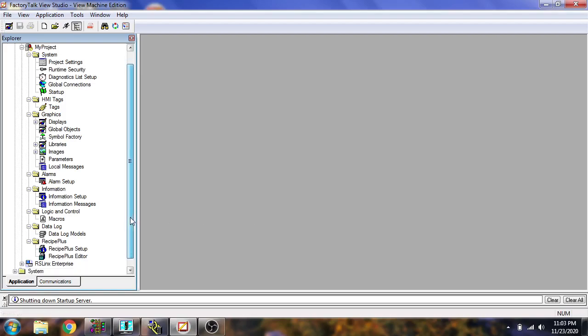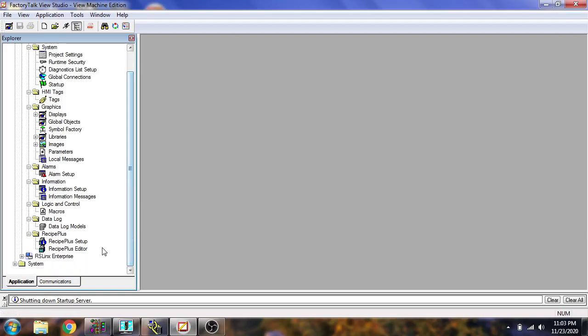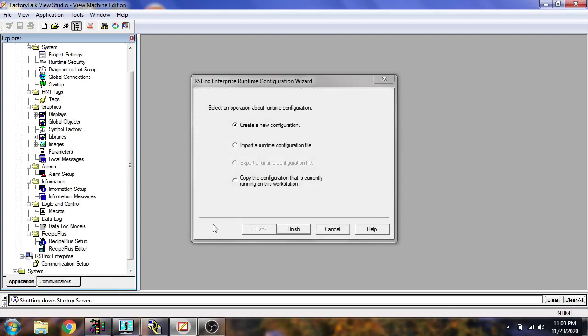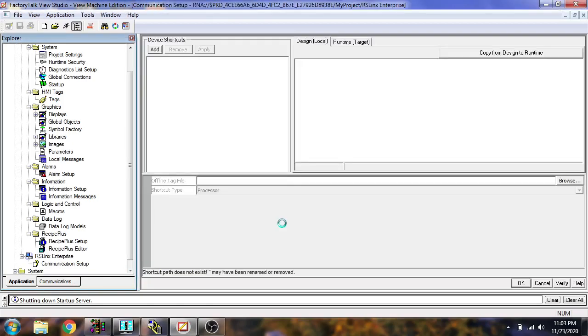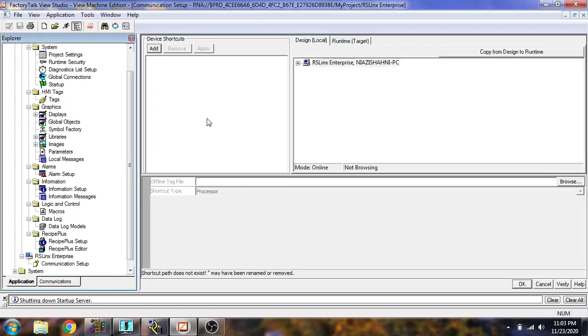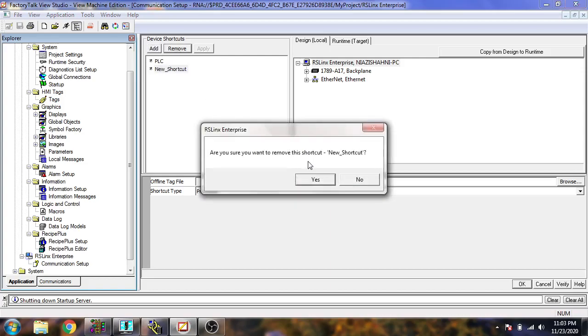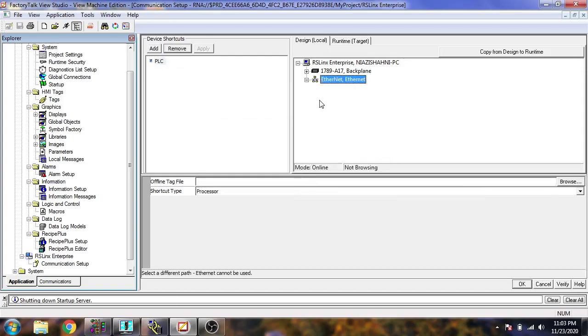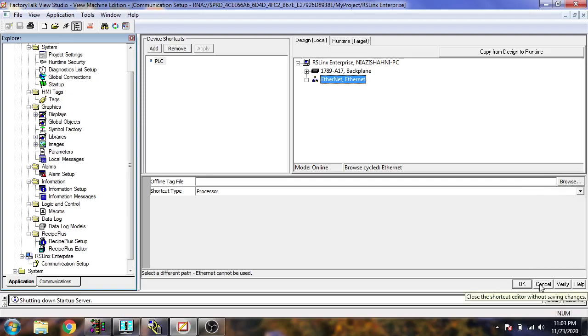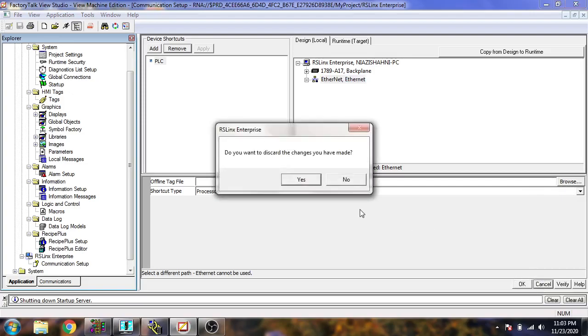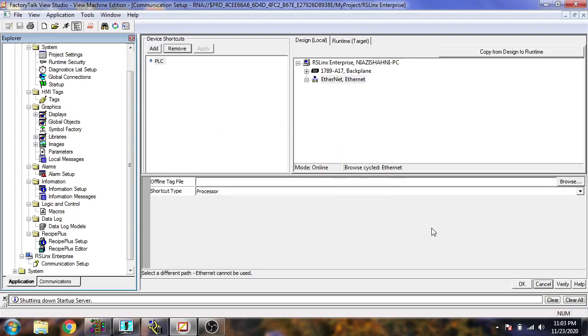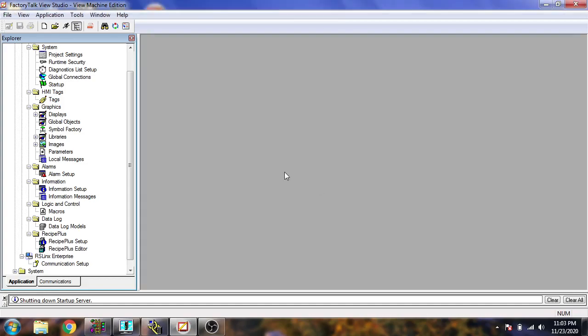I'm just showing you how you communicate to your RSLinx to your PLC. You will use RSLinx Enterprise and setup Communication Setup and create a new configuration. You will add a device which we will name my PLC, and you add then you just select your PLC there and you will connect that. Browse for tags - I have a browse offline tag available so you will check it from this. I'm going to cancel it, I just don't need to, yes I need to discard it.